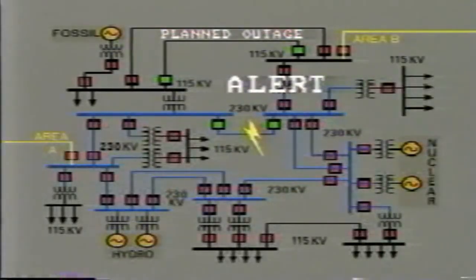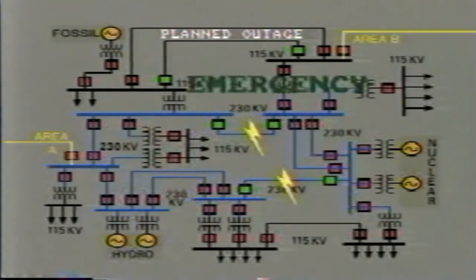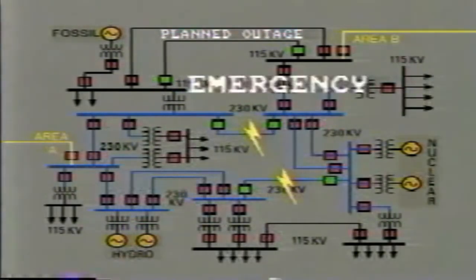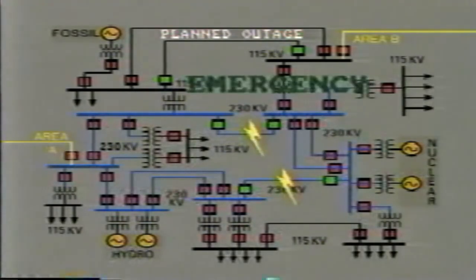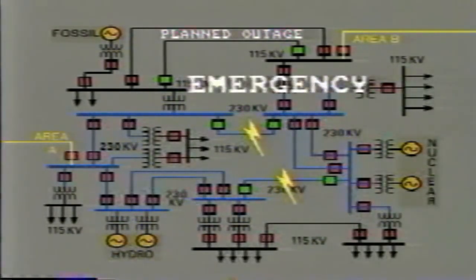However, supposing that yet another forced outage occurred before the line could be restored, now we have 3 outages. This system is now said to be in an emergency state. Some parts of the system may become severely overloaded and approach stability limits. It is likely that the system would not survive yet another additional forced outage. This would probably result in a cascading effect, with the consequence that generators and lines trip out due to instability.